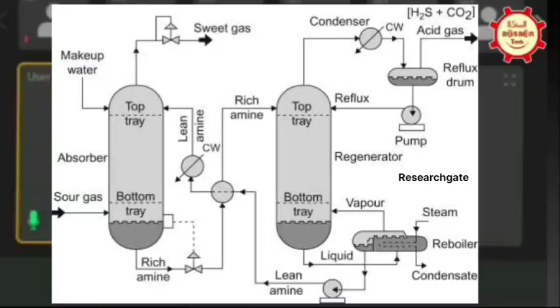And the top of the regenerator will be SS cladded. So basically, these two designs I have seen. If we go from the pump downstream of the flash drum till the regenerator, everything is SS, and there is no need for this PWHT issue, because amine SS is resistant to amine SSC. Only when you have carbon steel, even downstream of the lean-rich amine exchanger till the letdown valve, then you need to go for PWHT for the welds to control the hardness, to control amine SSC.